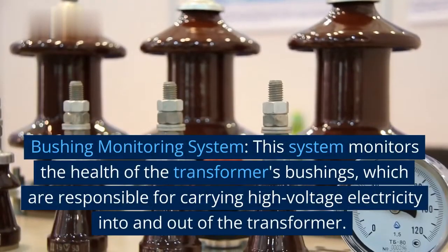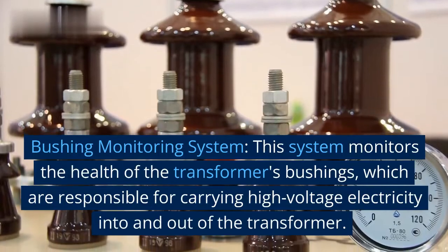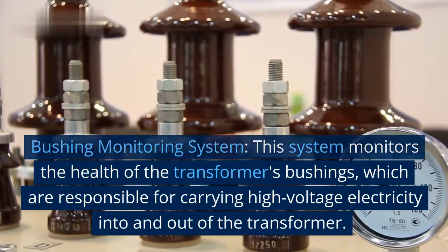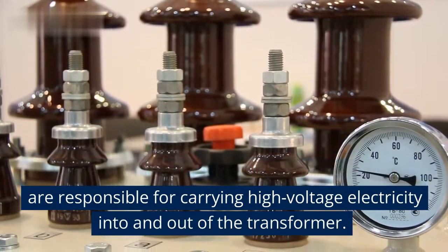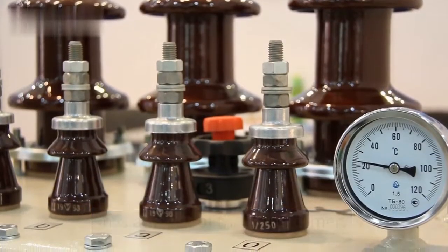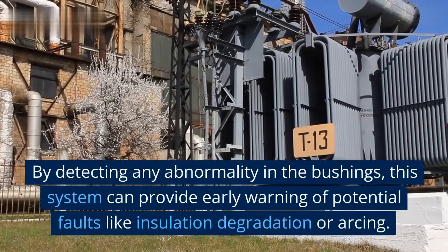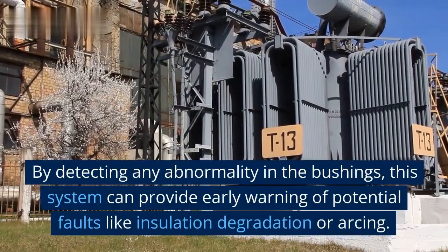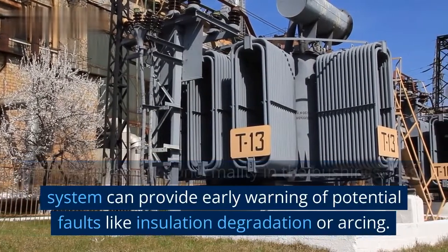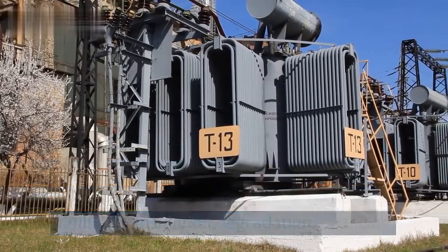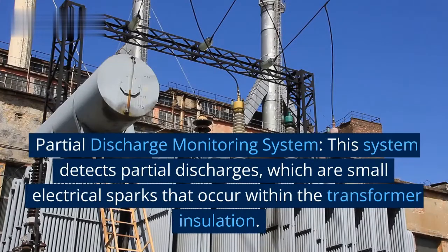Bushing monitoring system. This system monitors the health of the transformer's bushings, which are responsible for carrying high-voltage electricity into and out of the transformer. By detecting any abnormality in the bushings, this system can provide early warning of potential faults like insulation degradation or arcing.